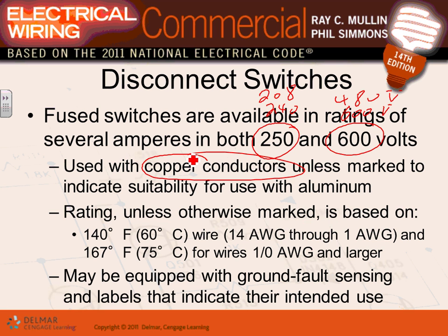And when you land your conductors on the terminals, the lugs, like everything else, guys, you go to the 60-degree column if your conductor is smaller. If your conductor is 1 aught or larger, then you go to the 75-degree column. We went through this, guys, when we talked about using the ambient of 310.15(B)(16).